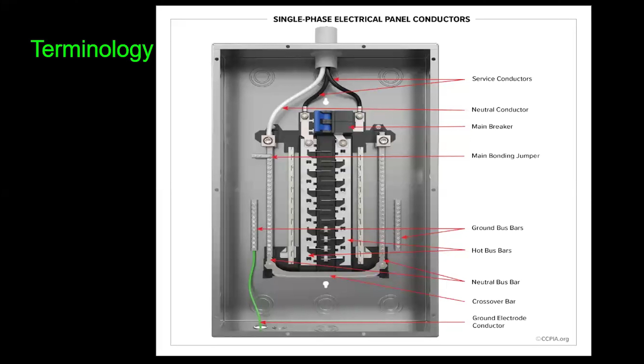Here's a bit more on the diagram showing how circuit breakers are put into place. The gutter posts are designed so your wires go on the outside. I worked on one of these panels once, and the way we used to do it, we'd bring the line all the way up and then down if it came from the bottom, or down and circle back up if from the top. A lot of panels nowadays just go right to the breaker. I kind of like the loop method because it gives you a little extra if you ever need it, but that's just personal preference.